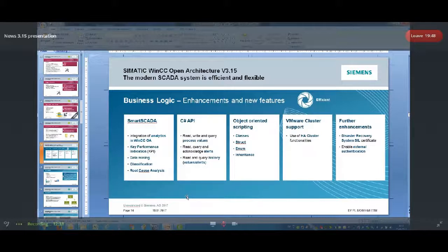And the system is doing a clustering for you, so that it finds different, similar system states, and you just need to specify, okay, classify what is what. Yeah, that was a failure because of the mechanical condition, this was another thing, and so on. And by doing that, you are training a random forest model for the system, and with that, we can then predict at any later point in time, when we use the actual values of the system, what is the system state? Is it in good shape?